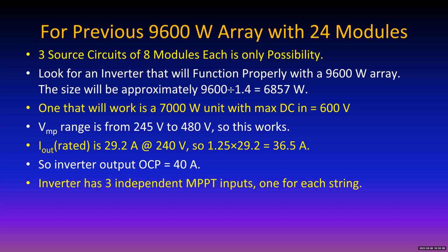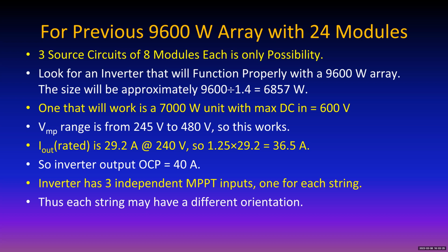3 independent maximum power point tracking inputs. Well, how nice. We can have those strings on different roof planes if you want. So here's a case where we've got 3 groups of 8, 1 for each string. That way you could have a string with a different orientation, or in fact, you could have 1 string of 7, 1 of 8, and 1 of 9, if they happen to come out that way, and each would have its own independent maximum power point tracking.